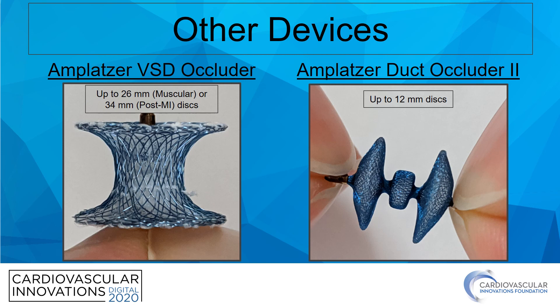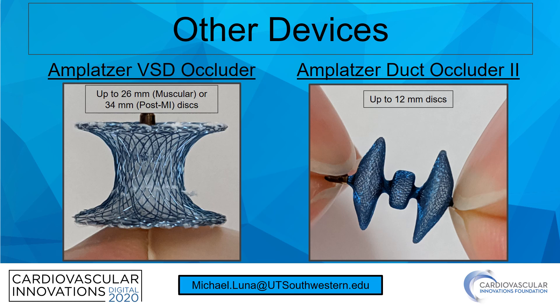A final thought: although off-label, you can consider other devices if available and you need to improvise. Two that can be considered are the Amplatzer VSD occluder and the Amplatzer duct occluder 2. The muscular VSD occluder has discs up to 26 millimeters in diameter and the post-MI VSD occluder has discs up to 34 millimeters, useful for large vascular structures. The ADO2 has discs up to 12 millimeters and is a very deliverable device. I'm happy to take questions by email at michael.luna@utsouthwestern.edu. Thank you.